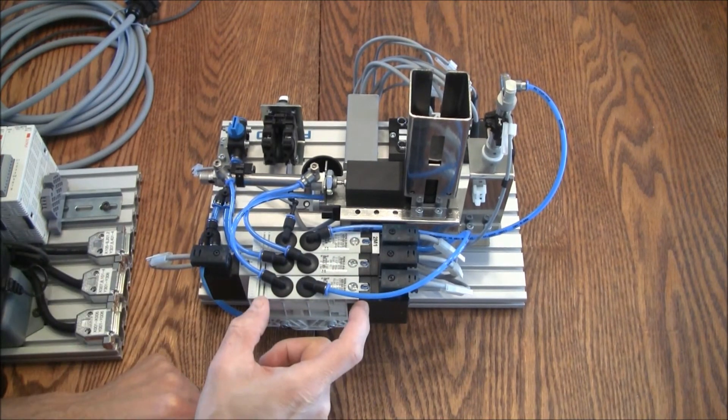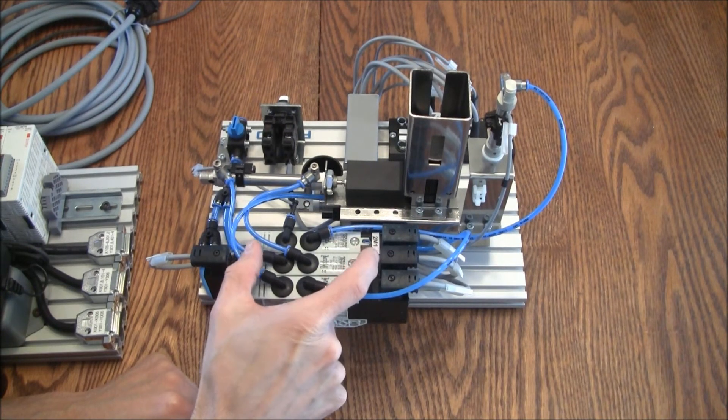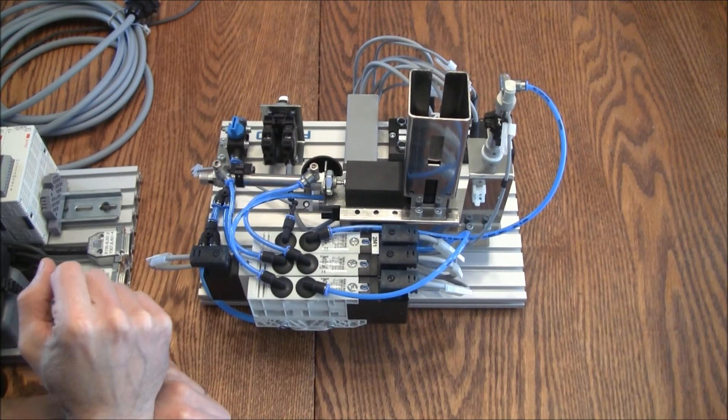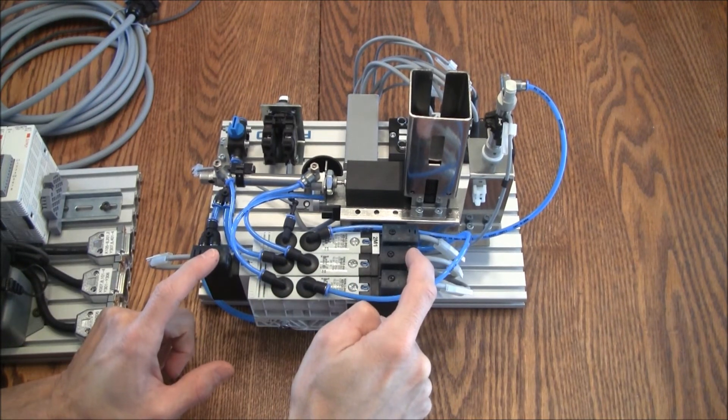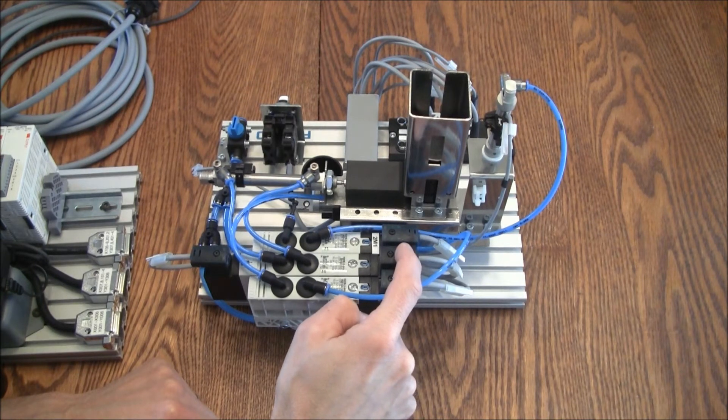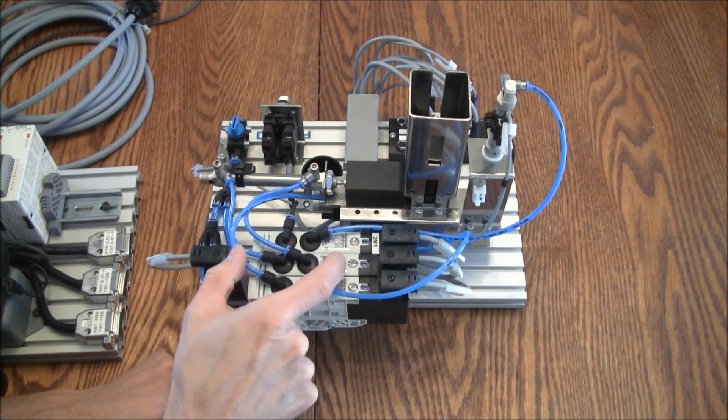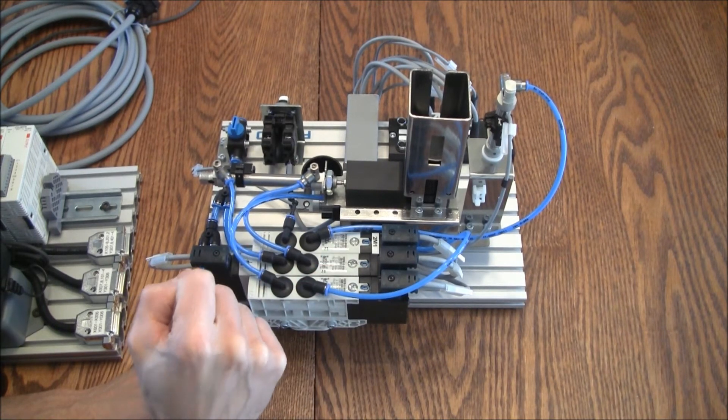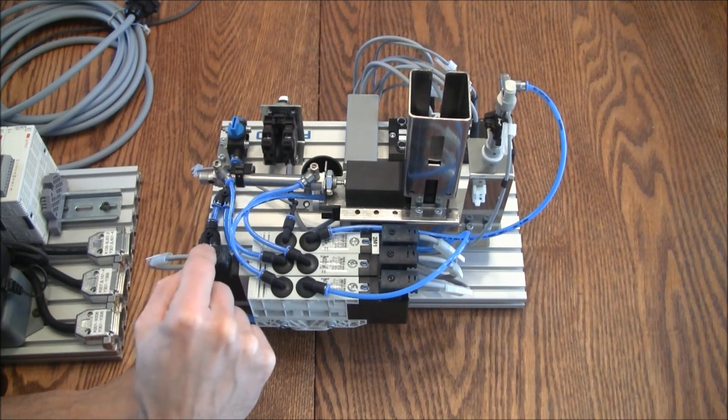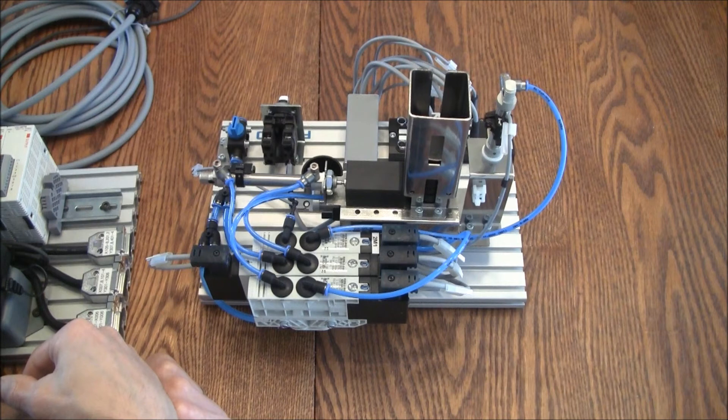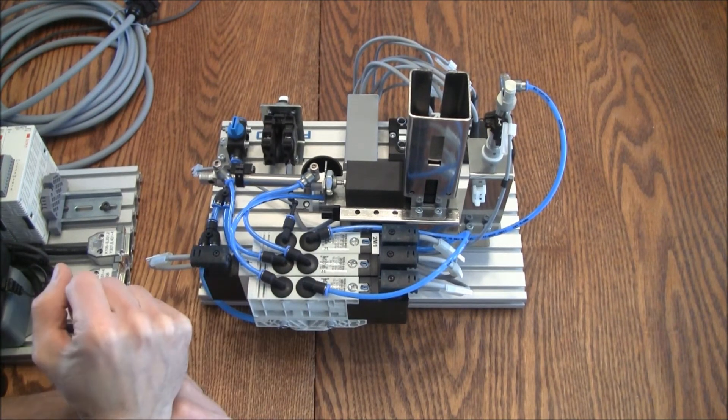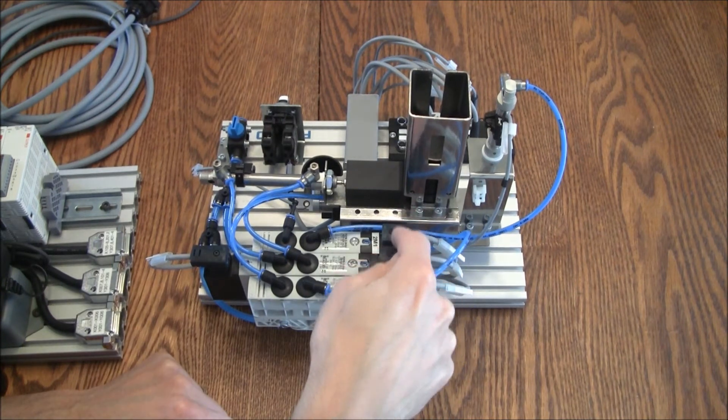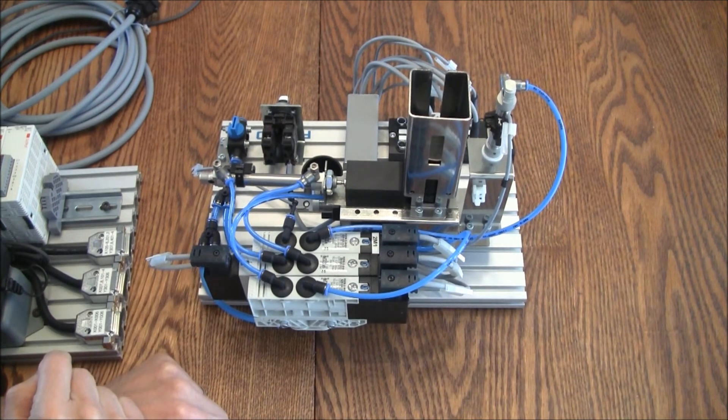Again, identical valve here doing the same thing. This middle one is also a four two-way valve, but it's double solenoid controlled. Meaning that when I energize the solenoid, the valve will shift. If I turn off, it will stay in that position. So it's detented. And then if I energize the other solenoid, it will move the valve in the other position, causing the cylinder to move in the opposite direction. And again, because it's detented, it will stay in that position. So that gives us our one, two, three, four outputs.